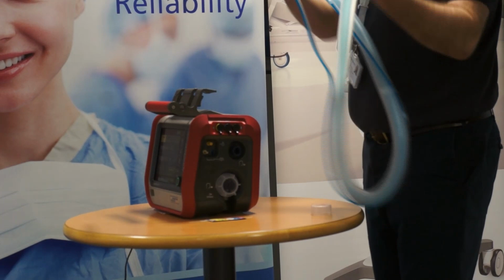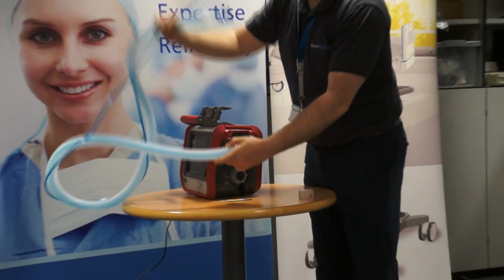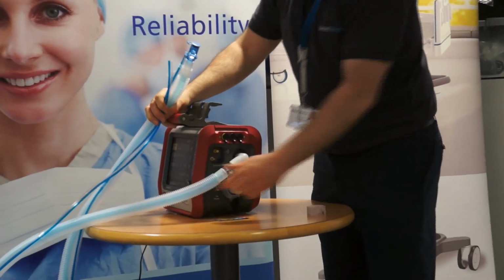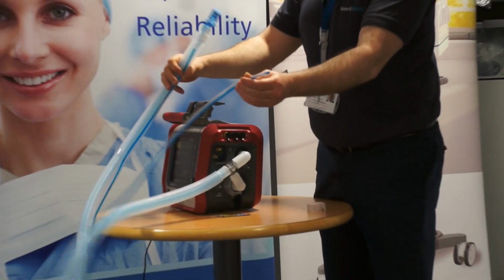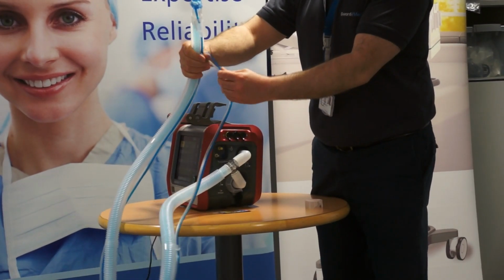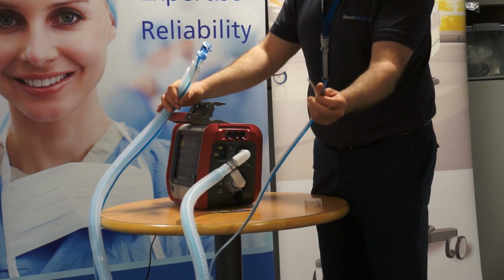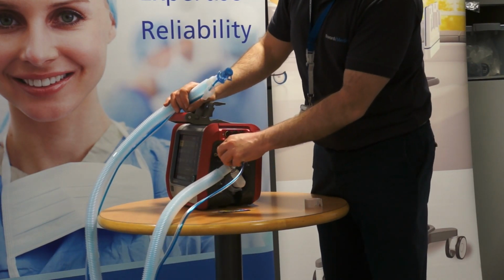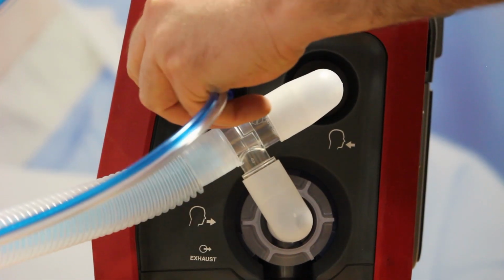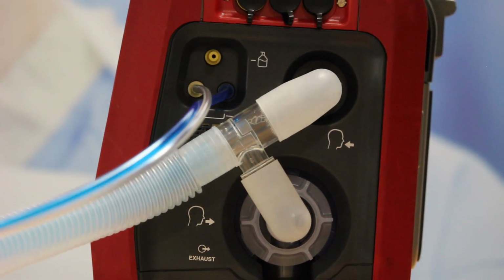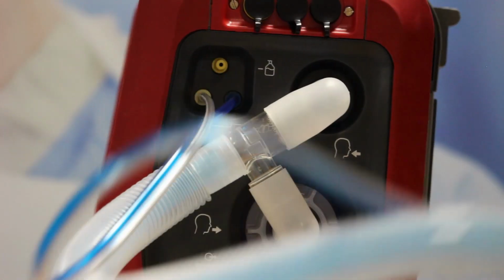Then the circuit itself plugs onto the ventilator just like this, pushes on like so, and then my flow sensor tubing is colour coded blue and clear. You need to peel the sensor tubing apart to give it some space, and then it plugs blue on blue, clear on white, and the circuit now is ready to test.